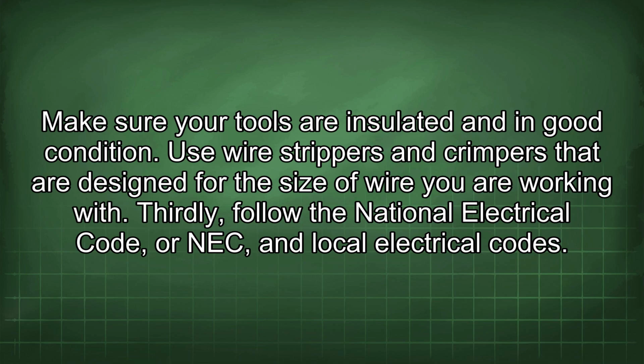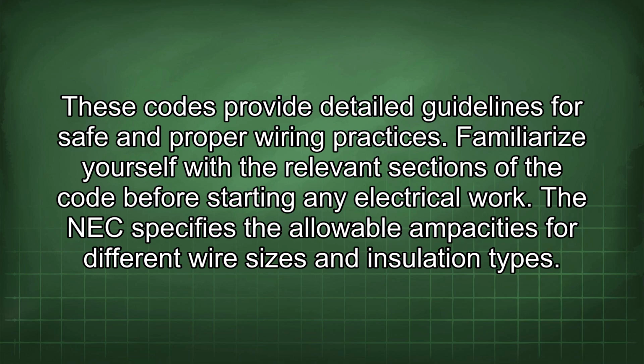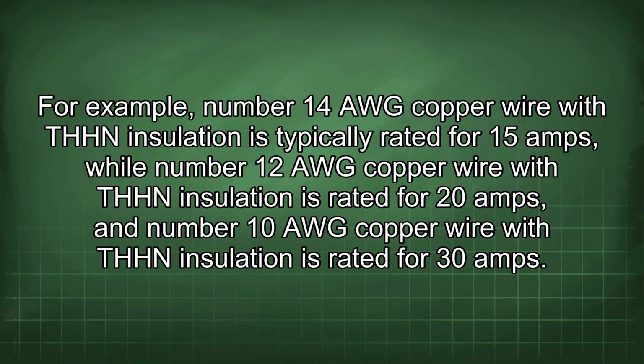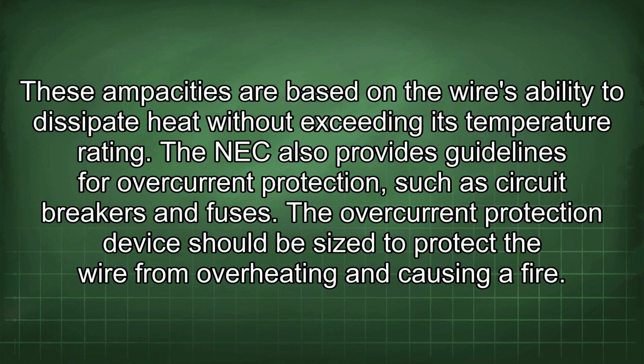Thirdly, follow the National Electrical Code, or NEC, and local electrical codes. These codes provide detailed guidelines for safe and proper wiring practices. Familiarize yourself with the relevant sections of the code before starting any electrical work. The NEC specifies the allowable ampacities for different wire sizes and insulation types. For example, number 14 AWG copper wire with THHN insulation is typically rated for 15 amps, while number 12 AWG copper wire with THHN insulation is rated for 20 amps, and number 10 AWG copper wire with THHN insulation is rated for 30 amps. These ampacities are based on the wire's ability to dissipate heat without exceeding its temperature rating.